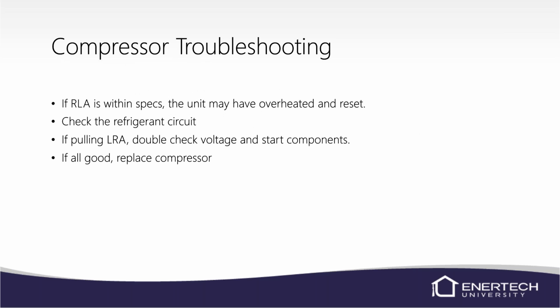If the run load amps are within specs, let's say on a 4 or 5 ton unit, the run load amps are going to be somewhere around 25, 27. Now, if you've taken amp draws quite a bit in the field, you know that we're normally not at the run load amp mark that we put in the manuals. We're usually considerably under it, 3, 4, 5 amps below it. That's not uncommon. So as long as we're within specs, the unit could have overheated and reset, so we're going to have to check the refrigerant circuit. If it is pulling lock rotor amps, double check the voltage and the starting components. If those are all good, then we're going to have to replace the compressor.